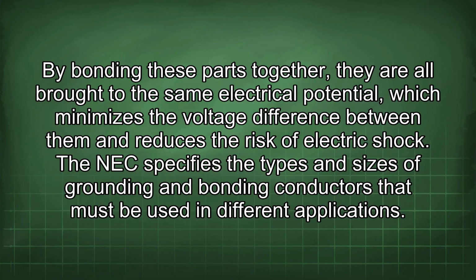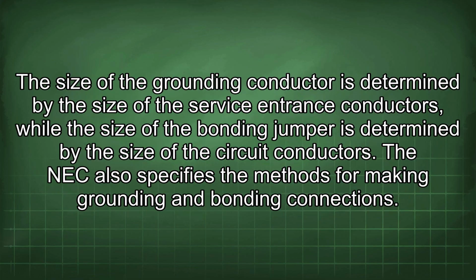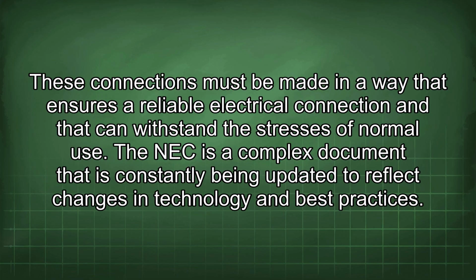The NEC specifies the types and sizes of grounding and bonding conductors that must be used in different applications. The size of the grounding conductor is determined by the size of the service entrance conductors, while the size of the bonding jumper is determined by the size of the circuit conductors. The NEC also specifies the methods for making grounding and bonding connections. These connections must be made in a way that ensures a reliable electrical connection and that can withstand the stresses of normal use.